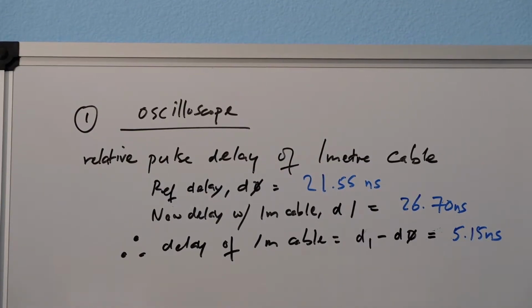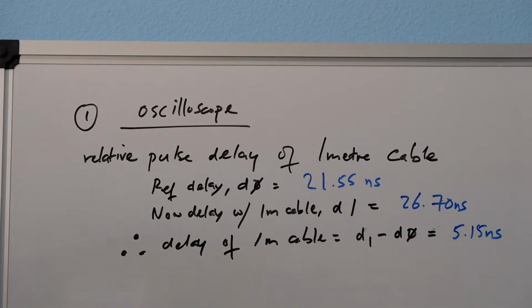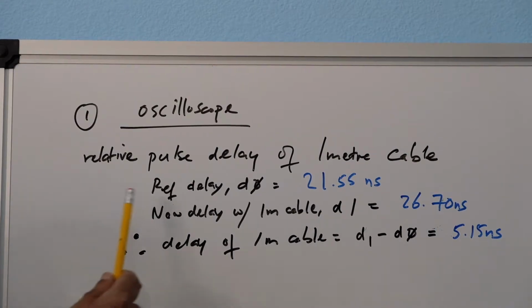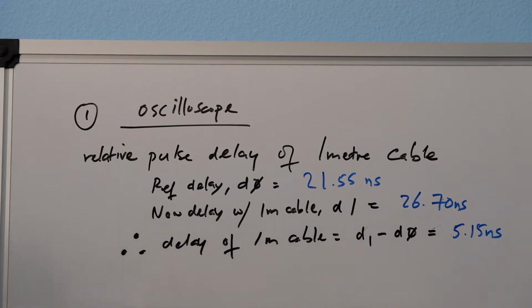So to do the calculations for the 3 methods, we'll start with the first method we tried with the oscilloscope. We had 2 signals going into the oscilloscope. One was basically a reference clock, which was to set the edge for the triggering, and the other signal was going into channel 2, which was the main signal we wanted to measure. We took those 2 cables and applied the 2 signals into the 2 channels of the oscilloscope, and set the reference delay for that particular measurement. We're not going to use that for the actual measurement, but we want to get a reference, and we got a reference delay of 21.55 nanoseconds. That delay includes various delays within the AWG itself, plus cable mismatch delays, delays within the scope, all the systematic delays that were there in the setup.